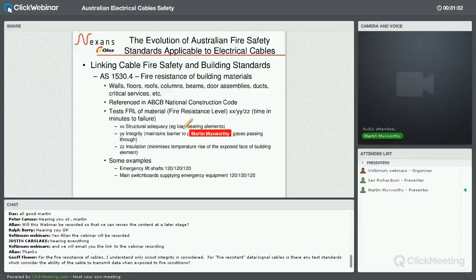The last slide looks briefly at the Australian Building Code Board, the National Construction Code that details fire safety systems in buildings. In reading some of the elements of the National Construction Code, you see that it talks about fire resistance of walls and floors and all sorts of common building components, and it develops a similar category or fire resistance level to that I've been describing in AS 3013. It describes a 3-part rating in this format, XX, YY, ZZ, and they relate to time in minutes to failure.